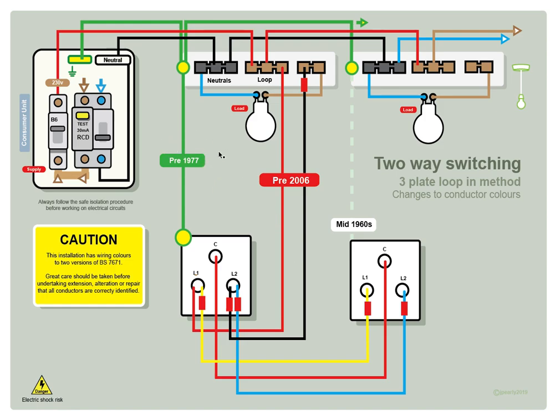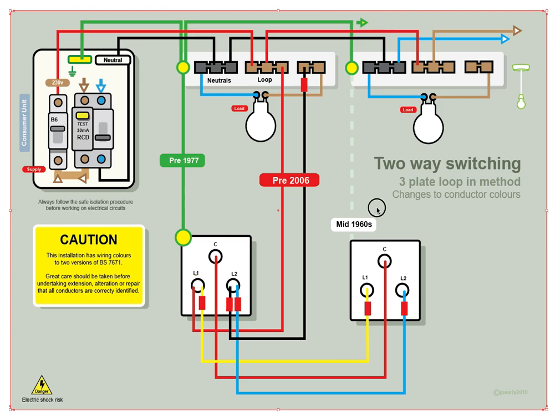And if you go back even further to pre-1977, you might see the CPC is just a solid green sleeving. It's a good way of dating installations, gives you an idea how old it is. You go back even further than that, you might find no CPC whatsoever at the switch. Mid-50s, it was no requirement to earth lighting circuits, so you might find that your switch hasn't got a CPC at all. If that's the case, it's always a good idea to get a CPC to it. What you don't do is you certainly don't put a metal switch plate on or a metal light fitting up, because if there is a fault, there's no protective conductor to take the fault back and operate the protective device.